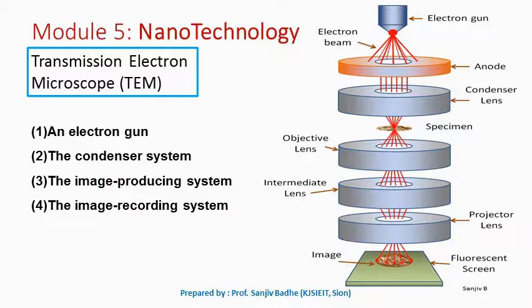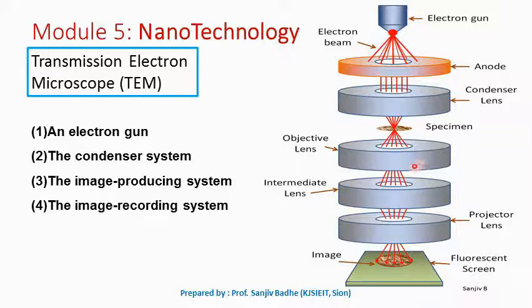Then we have the image producing system, which consists of an objective lens and an intermediate lens. These lenses focus the electrons passing through the specimen to form a real and highly magnified image. The objective lens is usually of a short focal length — 1 to 5 millimeters — and it produces a real intermediate image, which is further amplified or magnified with the help of a projector lens.